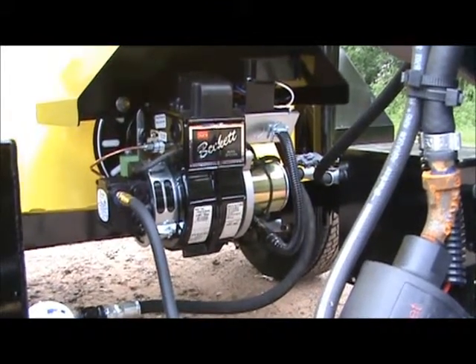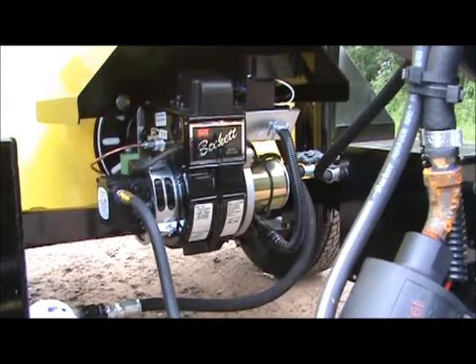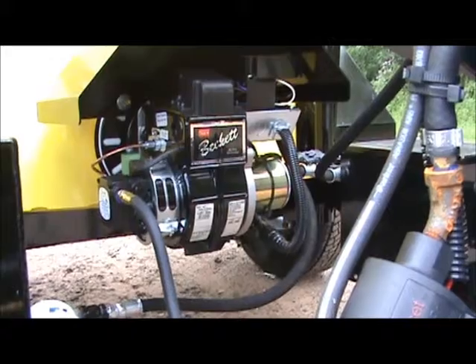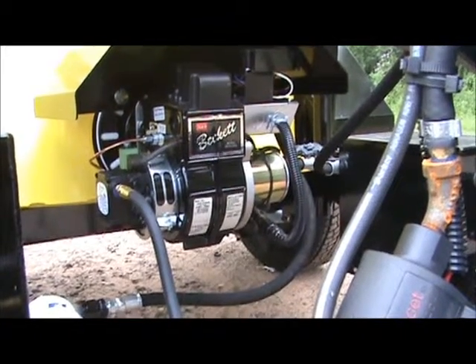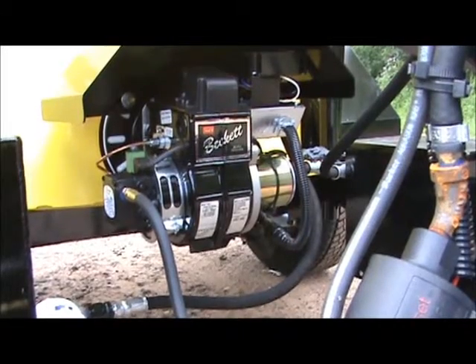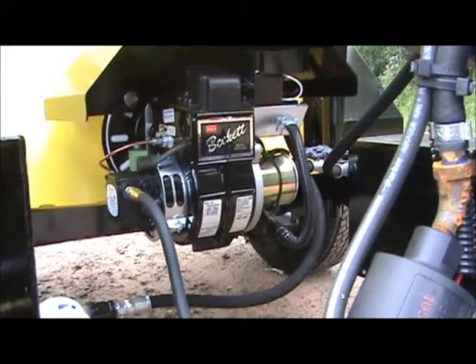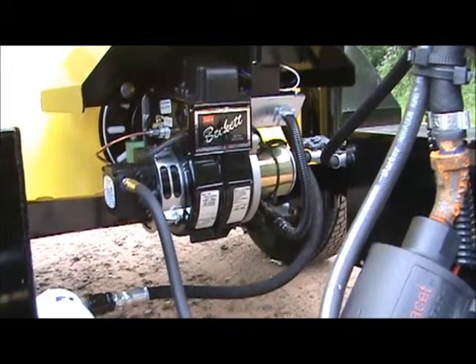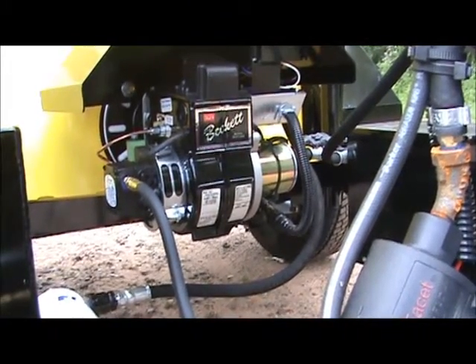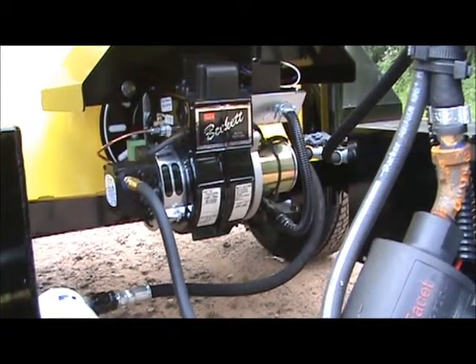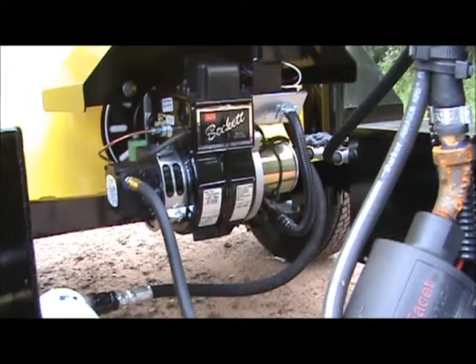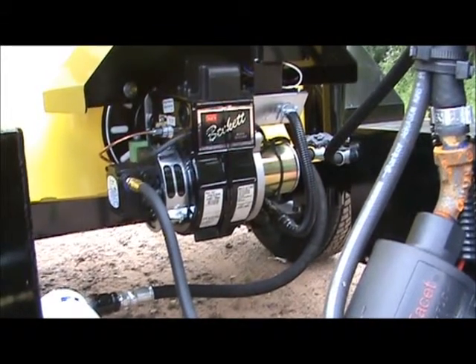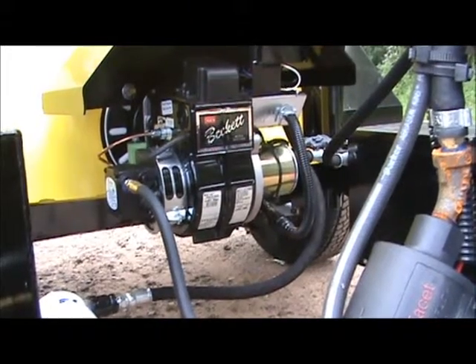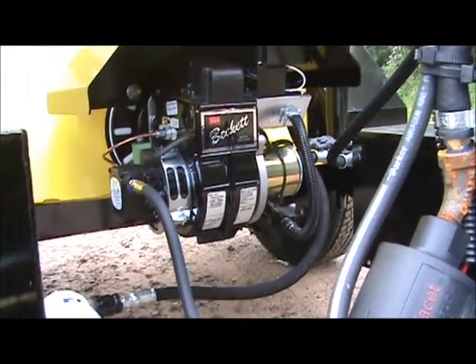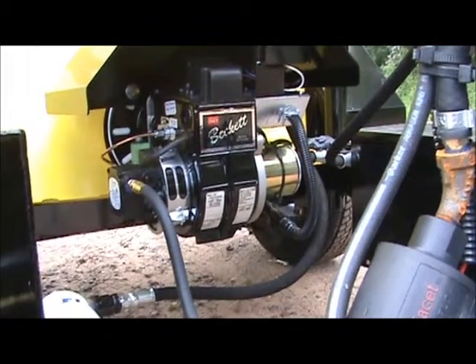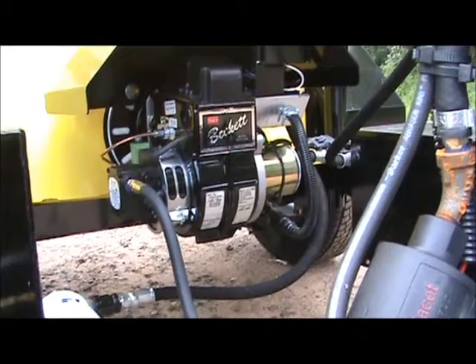Now, if you notice that stainless steel liner is real warped or collapsed, it's time to replace it. You're probably looking at anywhere from 500 to 1,000 hours, and you'll want to definitely be inspecting that and possibly even be changing that. Now, if you take that burner out and you stick a flashlight in there and you notice a lot of black soot or carbon, it probably means that we need a new nozzle on the end of the burner. The nozzles are about $12 or $15, so it's a very cheap replacement part. But what that's telling us is that we're not burning all the fuel. So you're getting a good spray, good atomization of fuel, and also a drip because the nozzle has started to wear out. So those are some maintenance things down the road that you want to keep an eye on.